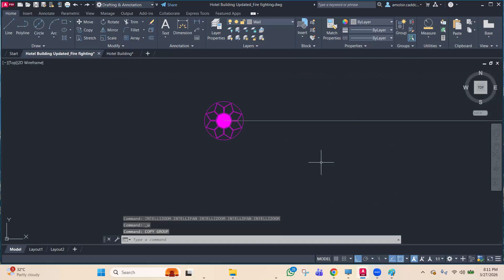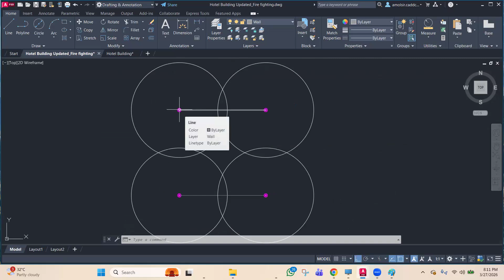See, sir, the maximum distance that we can take from sprinkler to sprinkler is 15 feet, which is 4.5 meter, 4500 mm. If I take 4500 mm as the maximum distance, you can see the dead zones are getting created over here. So this area is not covered. So you don't always have to take the maximum distance. We are having a range of distance. It should be between 7.5 feet to 15 feet.